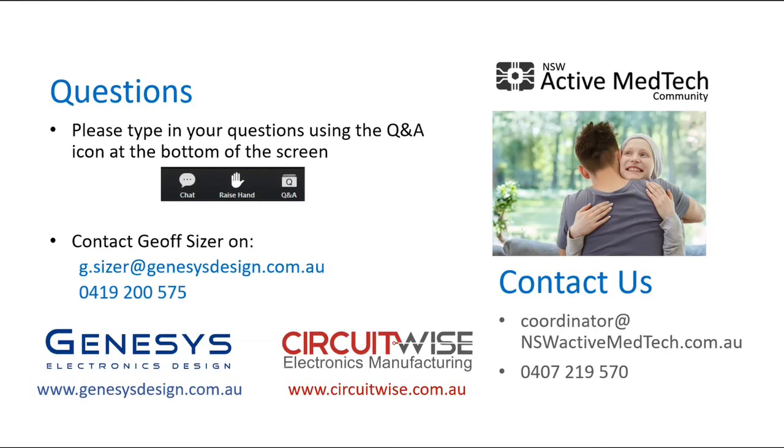So to answer the question, the pivotal clinical trial will typically occur after you have developed a device at least to engineering prototype stage and put it through design verification to show that it meets its requirements. So you can then rely on the fact that the device you are using in those pivotal clinical trials is representative of the final medical device. If it's not, then you can't necessarily claim that those clinical trial results have any validity, because you can't demonstrate what was the build status and software status of the device you used for them.